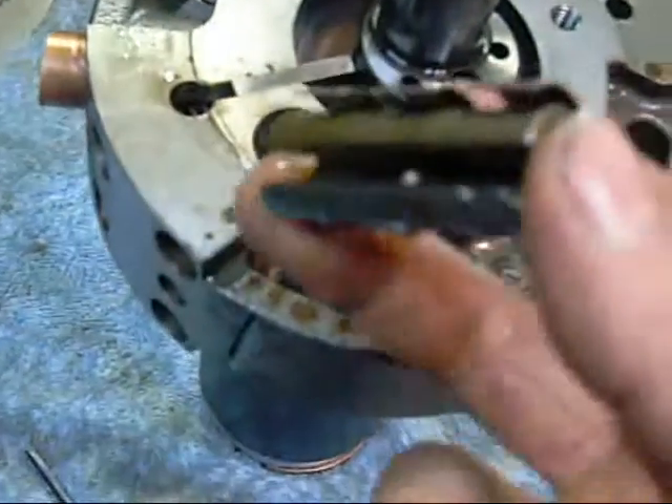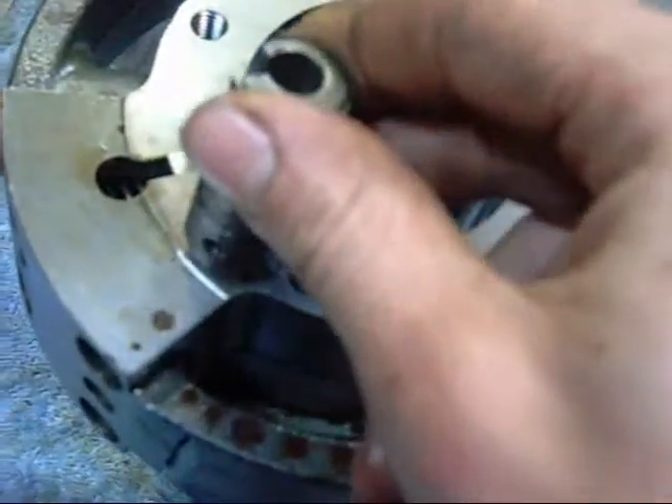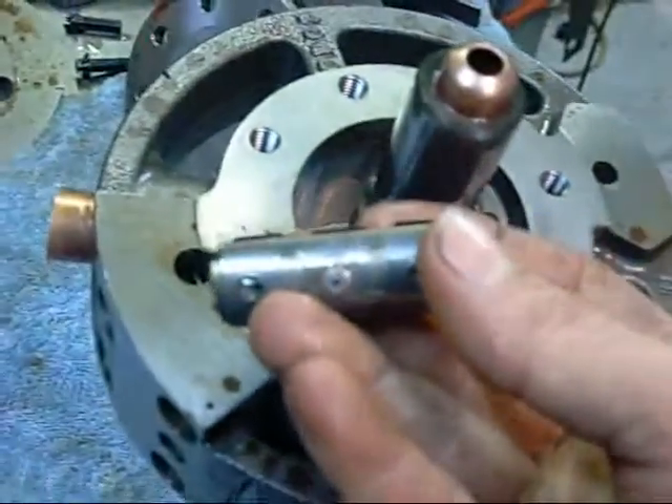Which is actually down through there — a little pin hole. The valves just act to check the flow, and when the compressor stops, in theory you shouldn't get any gas bleeding back through. It's just held in place with a couple of cap screws.